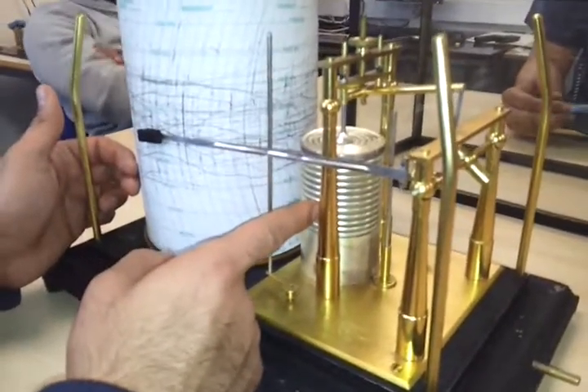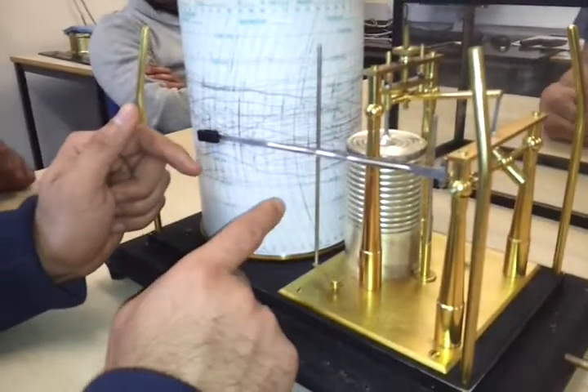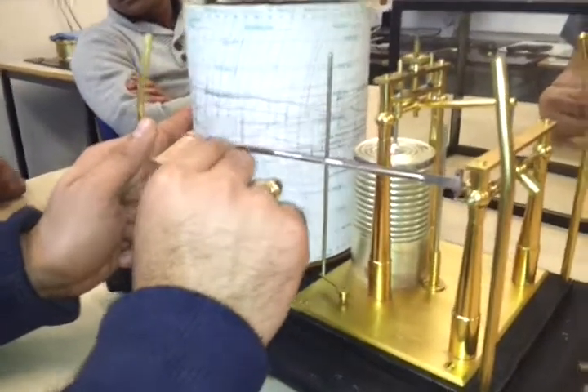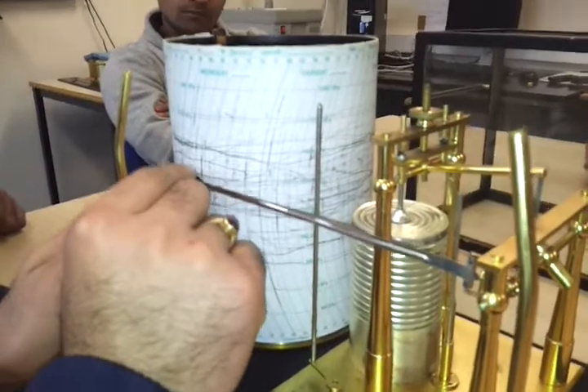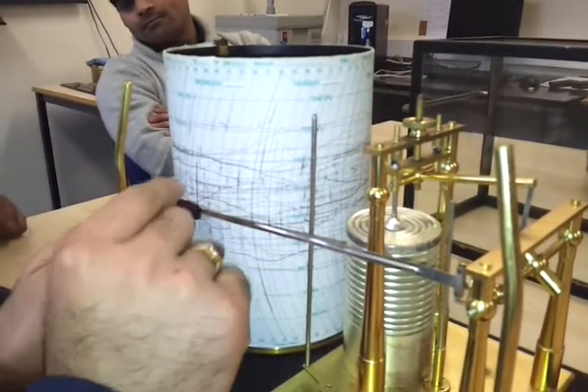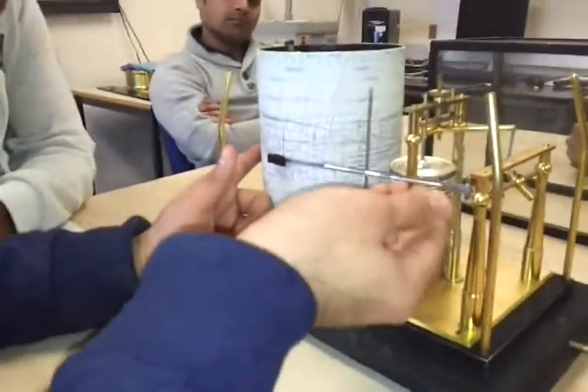The silicon oil that has been put, one more purpose is to reduce the vibration so that when your fiber nib is printing your atmospheric pressures, it doesn't draw any thick lines. It will draw the fine lines because the less vibration will be there in the instrument, the less thickening of lines you will get.